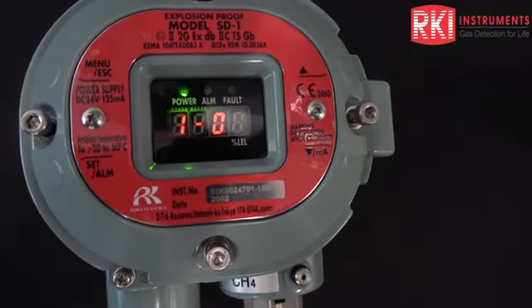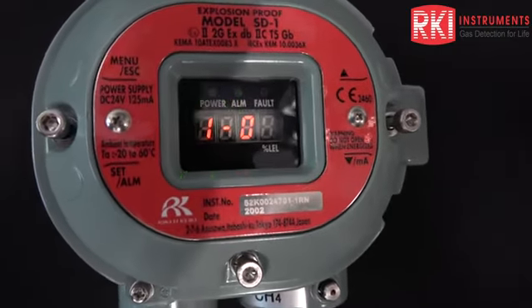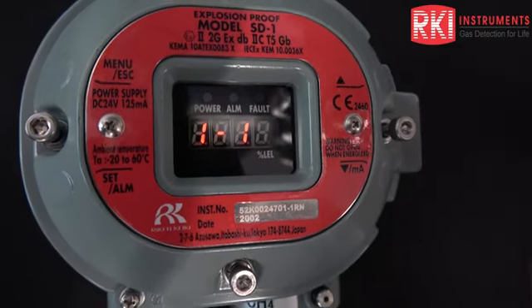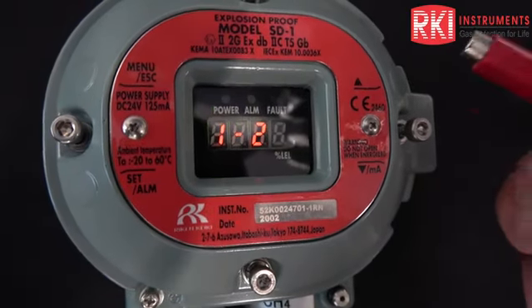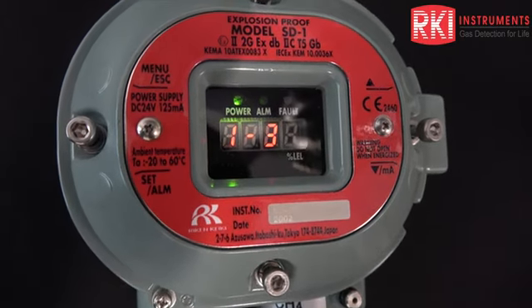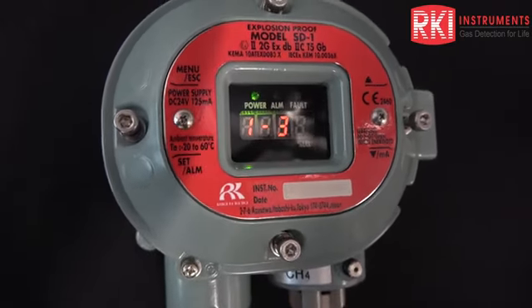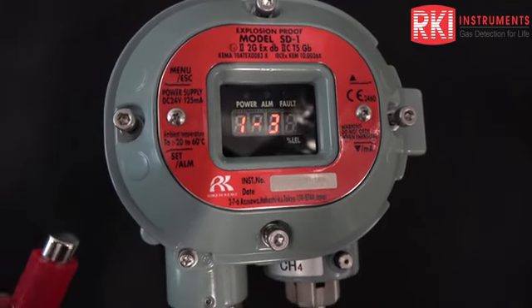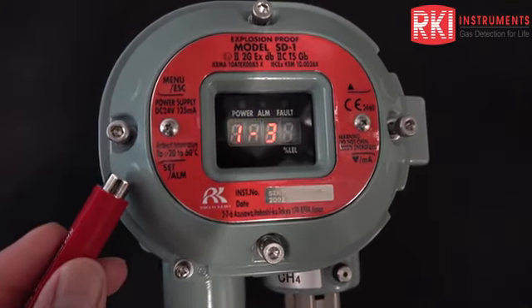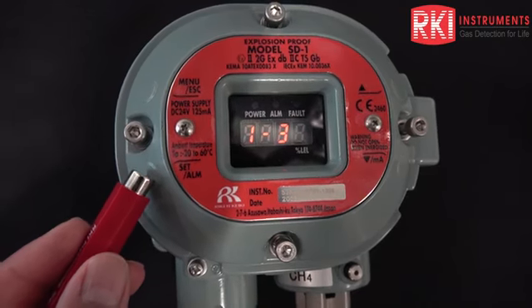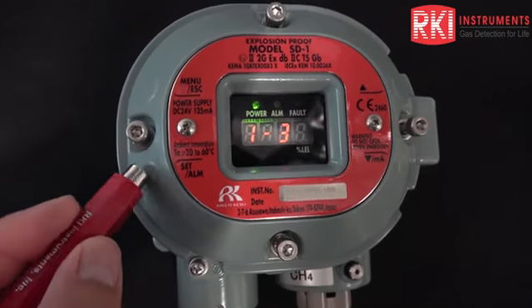So basically I want to get to 1-3. So I'll just use my magnet and just touch this top pad, and it's pretty sensitive, and I'm at 1-3. All right. Once I'm at 1-3, I can actually go into the calibration portion of the maintenance mode. And the way I do that is I go to the bottom pad on the left side, hold it down, or touch it, I should say.